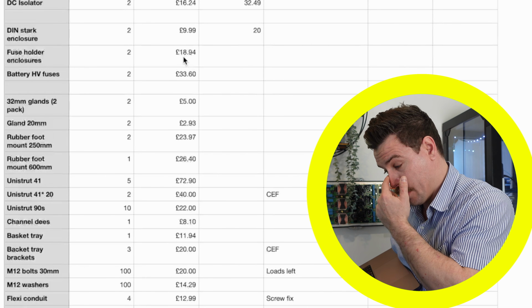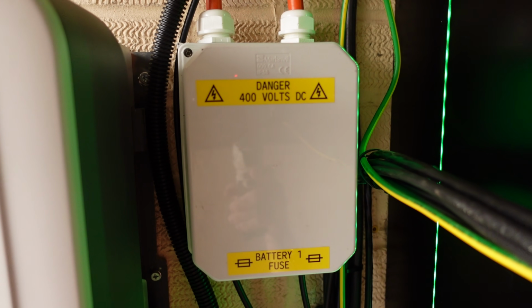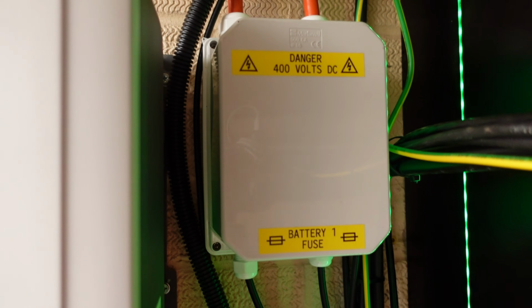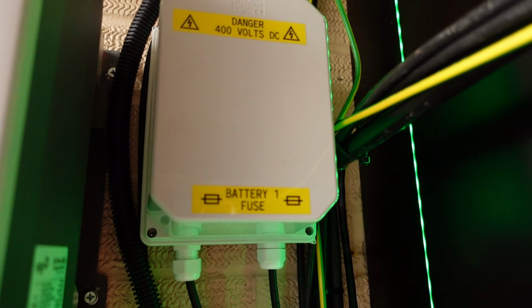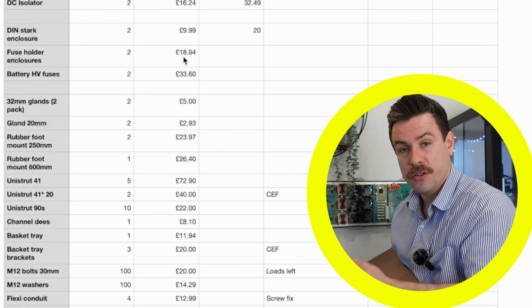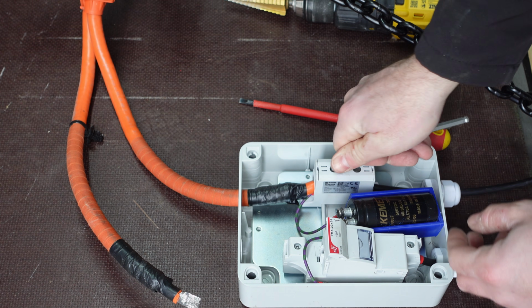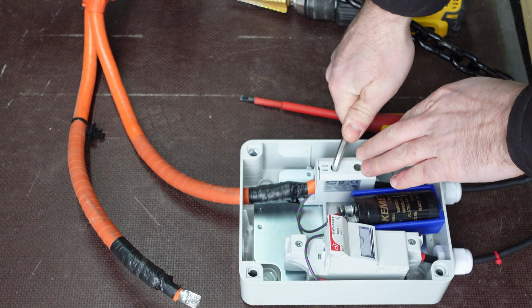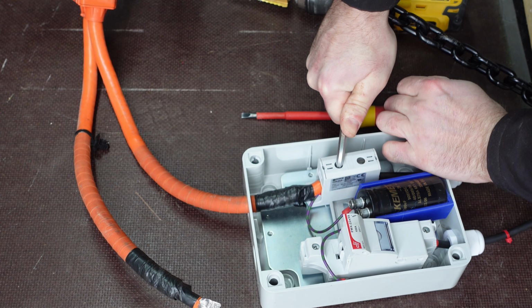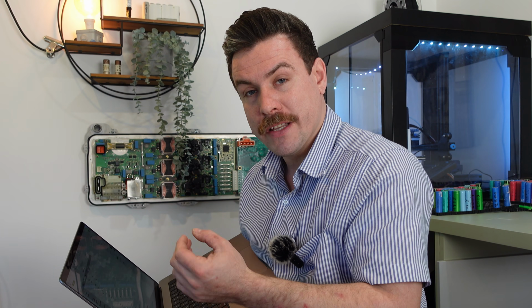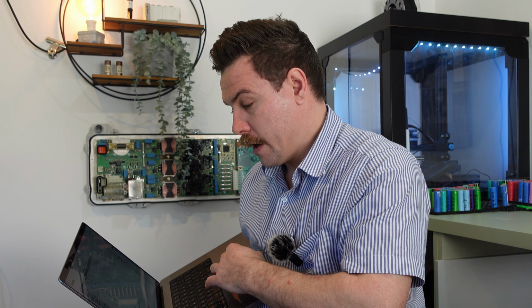We've then got the fuse holder enclosures. As soon as we come out of the battery, we want to fuse down to our DC cables. This is just a safe method of reducing the limit of current that can come out of that battery and keeping everything safe - you definitely want that before you step down a cable size.